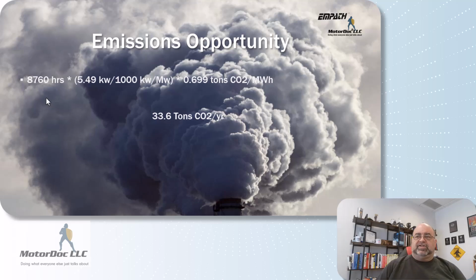Well, that, of course, I can calculate out. If I'm assuming 24/7 operation of the motor, it makes the numbers look bigger. 8,760 hours times 5.49 kilowatts divided by 1,000 kilowatts per megawatt. So if I convert this over to megawatt hours, basically, multiplied by the present value of 0.699 metric tons. A metric ton is 2,204 pounds.